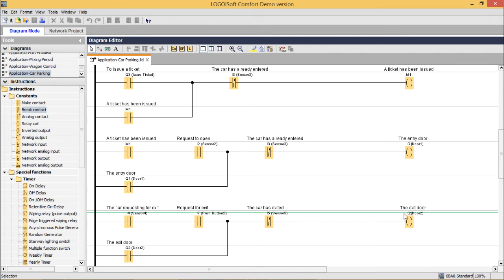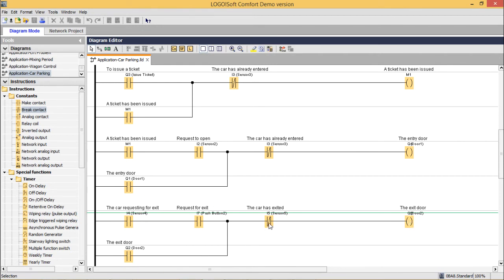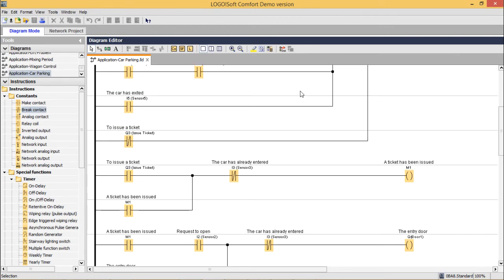That is why there is a latch on the entry door. For the exit door: the car is found on sensor 4 and the exit push button is pressed, requesting exit. The exit door Q2 opens and stays open via a latch until the car reaches sensor 5. The latch ensures that even when the push button is released and the car leaves sensor 4, the door remains open until the car reaches sensor 5 and successfully exits the system. This is the complete ladder diagram.